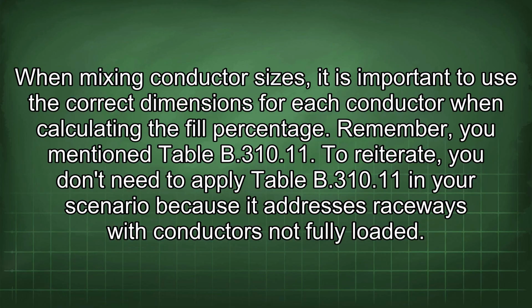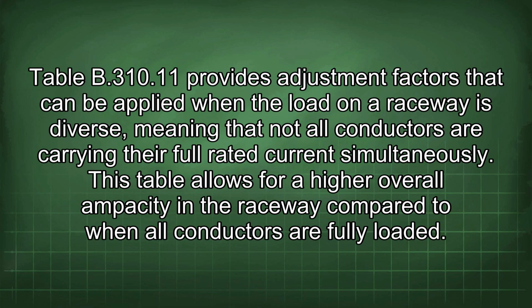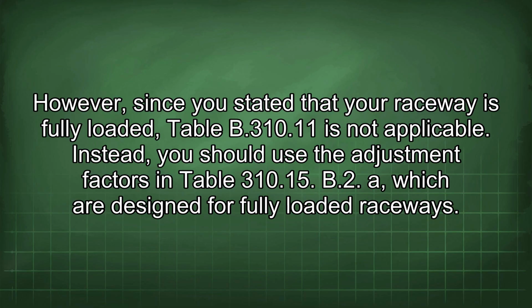Remember, you mentioned Table B.310.11. To reiterate, you don't need to apply Table B.310.11 in your scenario because it addresses raceways with conductors not fully loaded. Table B.310.11 provides adjustment factors that can be applied when the load on a raceway is diverse, meaning that not all conductors are carrying their full rated current simultaneously. This table allows for a higher overall ampacity in the raceway compared to when all conductors are fully loaded. However, since you stated that your raceway is fully loaded, Table B.310.11 is not applicable. Instead, you should use the adjustment factors in Table 310.15(B)(2)(a), which are designed for fully loaded raceways.